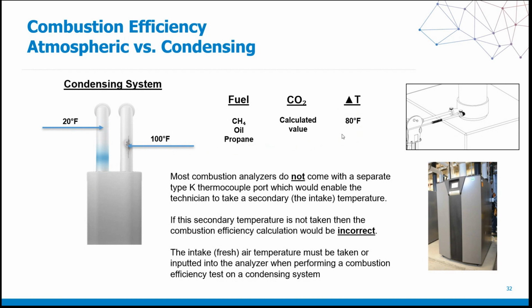Having such a high swing between those two numbers, in this case 50 degrees between the 70 and the 20, can produce upwards of an 8 to 9% swing in combustion efficiency. Remember, you must take a reading of the outdoor air temperature in order to get a proper combustion efficiency of a condensing system. However, if for some reason you don't have a separate type K thermocouple port, you can manually override in most analyzers, at least in Sauermann's or my company's analyzers. We give you the ability to manually input the outdoor air temperature. When you input that, you will be able to produce the correct combustion efficiency number for that high efficiency, otherwise known as condensing, appliance.